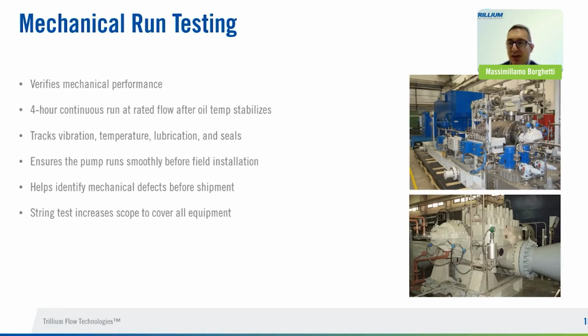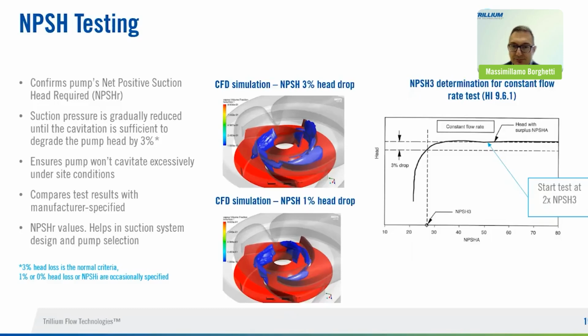A special case is the string test, where the scope of the test is enlarged. Basically, it is not limited to the centrifugal pumps only, but the scope covers all the equipment that is in the train. So the pump for sure, but we can have the driver, we can have the seal system installed, we can have lube oil when it is required, variable frequency driver, fluid coupling, we can have a gearbox. Let's say all the components that are inside the train are properly tested in the string test. Okay.